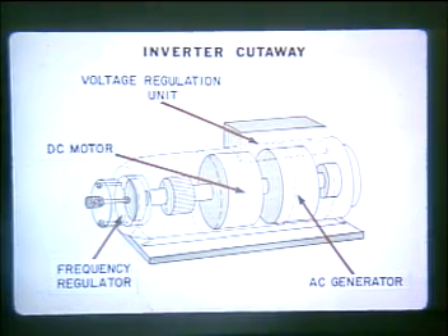The inverter is simply a direct current motor turning an alternator or AC generator on a common shaft. As a self-contained unit, the inverter maintains a regulated frequency and AC voltage output, contains the necessary filtering devices to eliminate radio interference, and limits its current consumption during starting. Each inverter is capable of furnishing 2500 volt amperes of power when operating from 27.5 volts DC. The total aircraft AC requirements are approximately 900 to 1300 volt amperes, so each inverter has a capacity well above the total aircraft requirements.